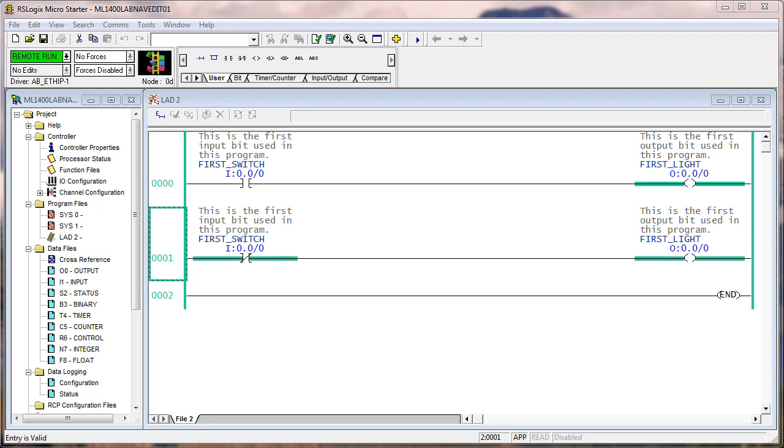The last couple questions there: why does it not reflect the logic of these 2 rungs? Last man wins. Can both of these rungs ever be true simultaneously? No, they cannot, because you have a true if on, true if off, pointing to the same memory location. So one of these instructions has to be false. Can both of these rungs ever be false simultaneously?